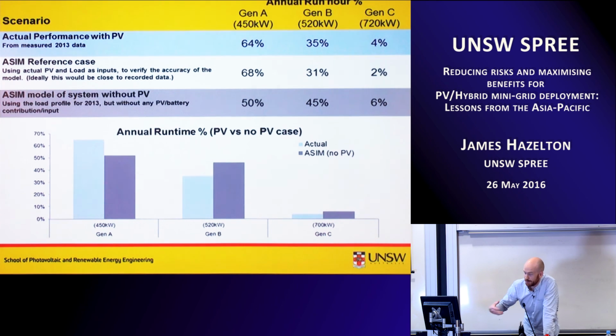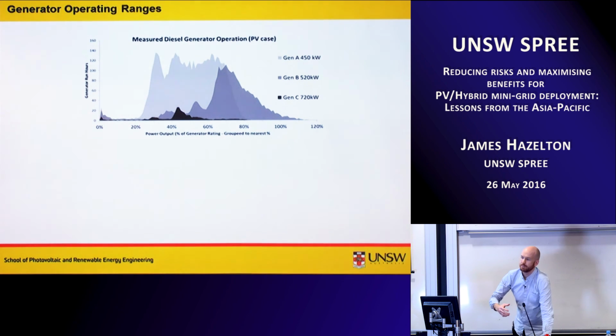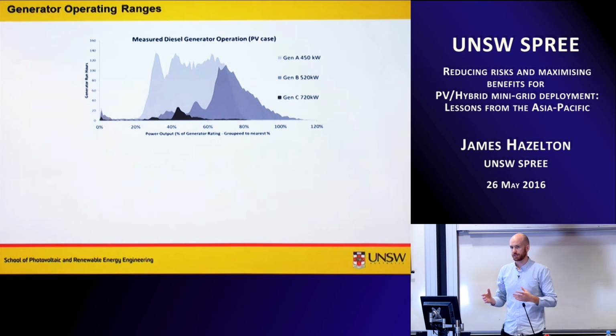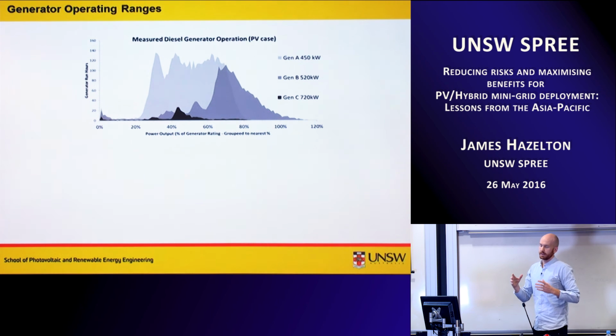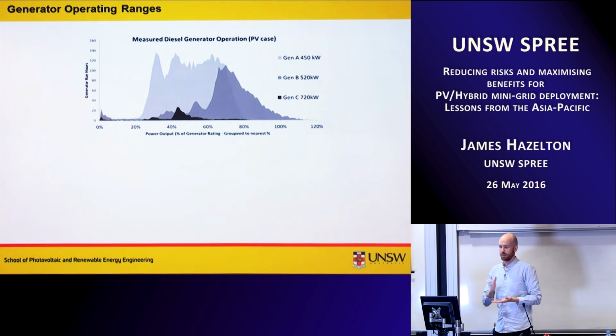This all contributes to acknowledging some of the benefits and the risks because, as I'm about to show, when you have PV penetration, this is from Tea Tree, coming into the system, you're actually pushing that smaller diesel generator lower and lower on its operating curve. And diesel generators don't like that because they operate at a lower temperature when they're operating at a lower power output.